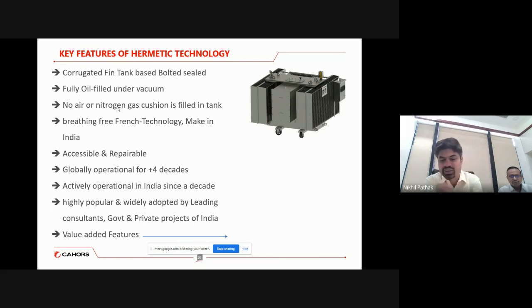I will, in coming slides, show you the inner view of the corrugated tank so that you will understand more on this. So widely this is a French technology, Make in India approach that we are following, which is nothing but the breathing-free technology. In common words, we say hermetically sealed technology is nothing but the corrugated fin tank, base bolted sealing with oil filling, 100% oil filling under vacuum conditions without adding any gas cushion. So it's a non-gas cushion transformer, breathing-free approach with French technology, Make in India concept. Because we have the factory located in Pune, it is giving a Make in India approach, and as I already said, it is accessible and repairable.